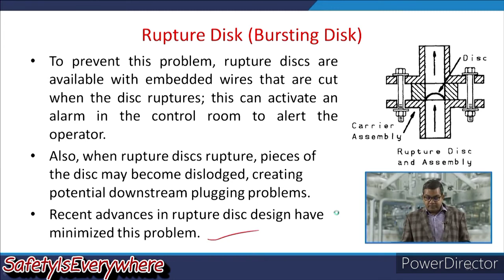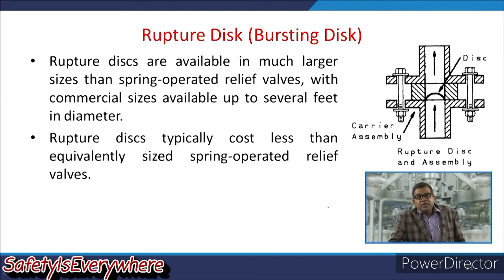Now these rupture discs are available in much larger sizes than the spring operated relief valve, with commercial sizes available up to several feet in diameter. These rupture discs typically cost less than the equivalently sized spring operated relief valve, and moreover the maintenance and other things are on the lower side for these rupture discs compared to the spring operated relief valve, where you need to perform regular maintenance.